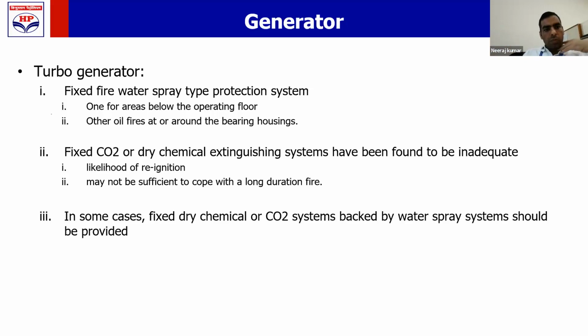Now, why these requirements are given is that people found that if you try to extinguish turbine fires with CO2 or DCP, then there is a likelihood of reignition. And sometimes the quantity of DCP or CO2 may also not be sufficient to cope with long-duration fires. If you are connecting fire water, then you can fight the fire for hours altogether. But CO2 and DCP have a limit, a limited time period. So for that reason, it is felt that the primary firefighting system for a turbine will be fire water spray.